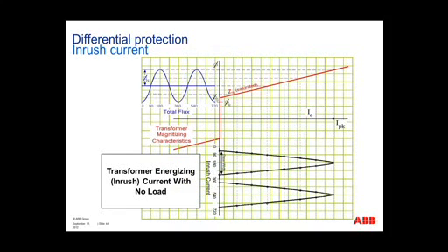So how do we detect inrush current? Well, with the relationship to this total flux, the current seen going into the transformer will not have the 60 hertz characteristic. It will have a 120 hertz characteristic footprint. And that's what I'm trying to show on this graph, that the footprint of the current going into the transformer is going to be at a second harmonic characteristic. So if there is a way to monitor that second harmonic characteristic, you would know you're in an inrush condition. And that's how the microprocessor relays see this inrush condition, by looking at the current flow at the second harmonic.